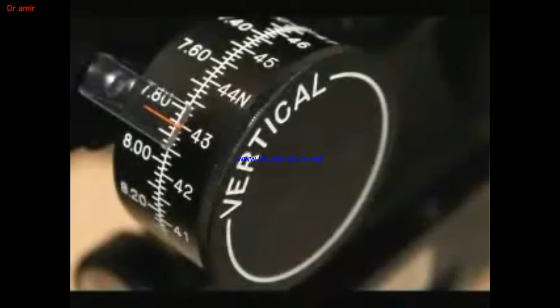Now you're going to follow these same exact steps for the left eye. The scale of the horizontal measuring drum indicates the dioptric power of the cornea along the horizontal meridian. The meridian indicators on the axis scale are white lines. Horizontal axes fall plus or minus 20 degrees around 180. The scale of the vertical measuring drum indicates the dioptric power of the cornea along the vertical meridian. The meridian indicators on the axis scale are white lines. Vertical axes fall plus or minus 20 degrees around 90.